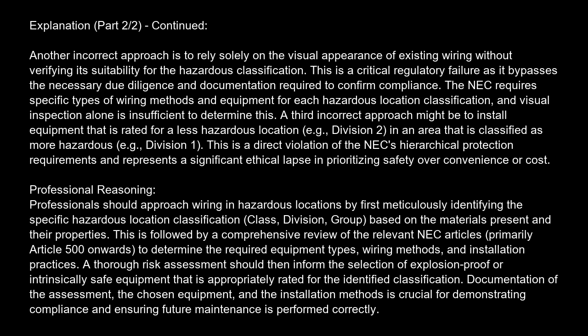A third incorrect approach might be to install equipment that is rated for a less hazardous location, e.g., Division 2, in an area that is classified as more hazardous, e.g., Division 1. This is a direct violation of the NEC's hierarchical protection requirements and represents a significant ethical lapse in prioritizing safety over convenience or cost. Professional reasoning.